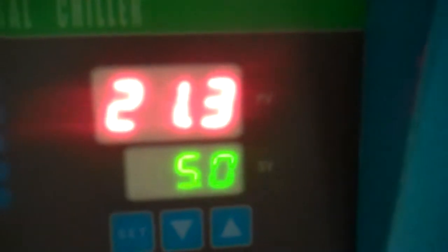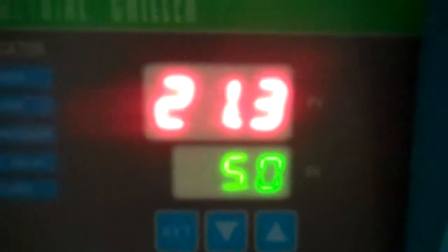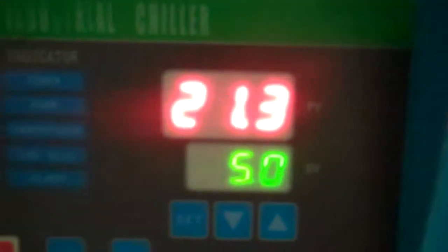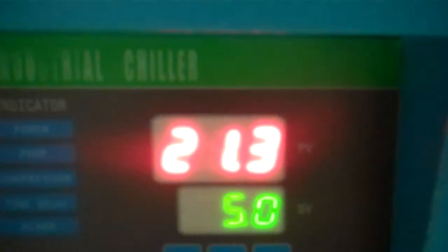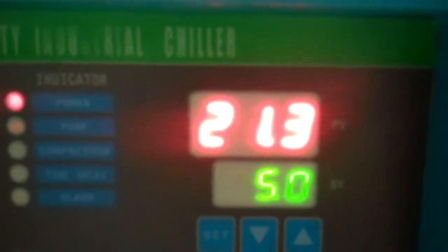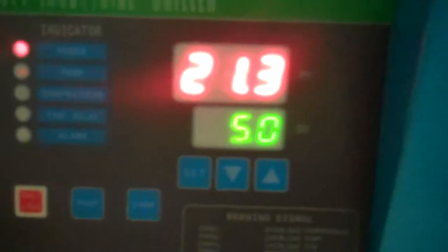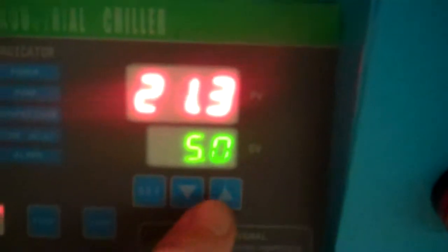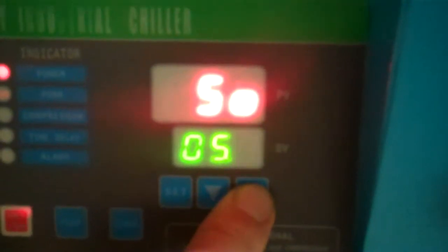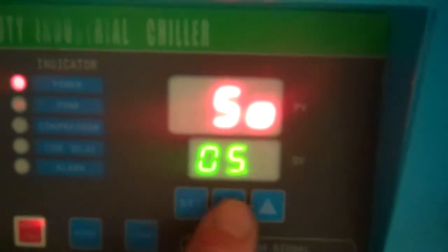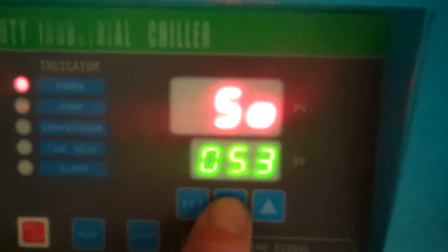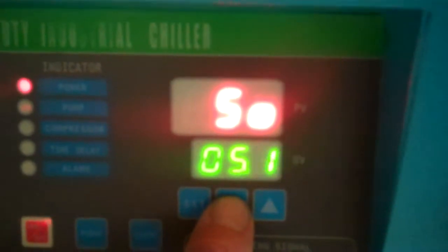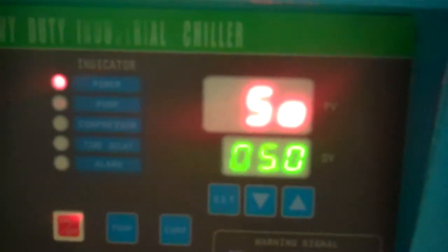These units run from 5 degrees to 25 degrees centigrade, which is basically 41 degrees Fahrenheit to 77 degrees Fahrenheit. To change the set value, you simply press set, and you can move it up to 25 C. For this case here, we're just going to bring it down to 5 degrees C.